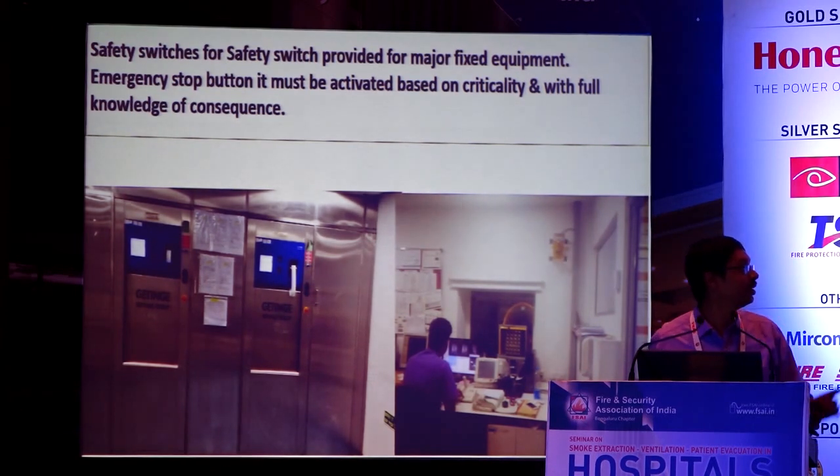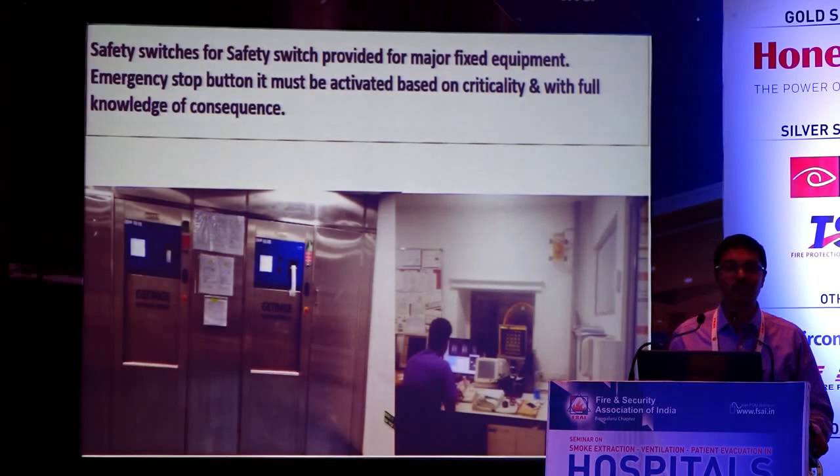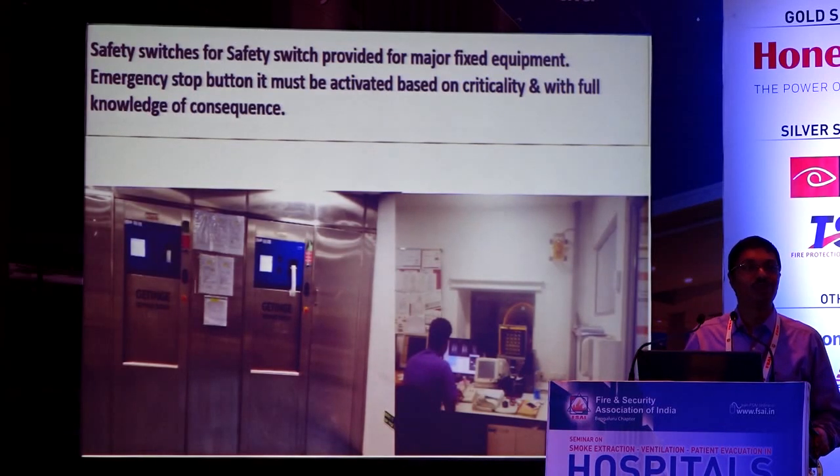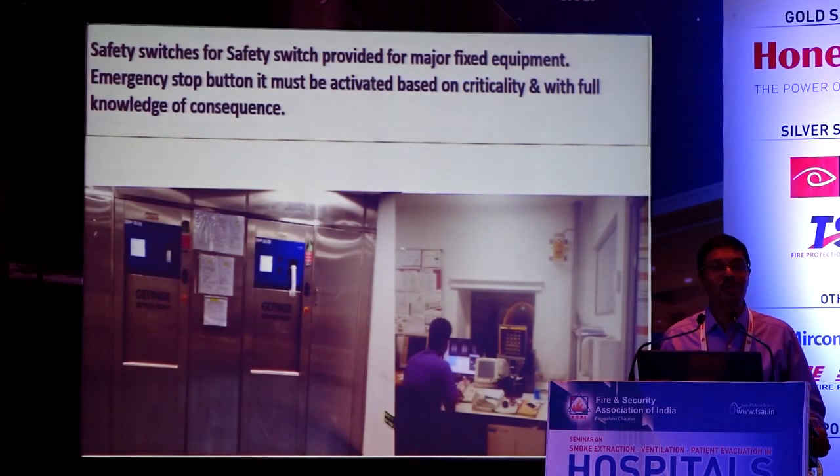The safety switch can be used only when it is needed, when somebody is stuck, because when you use that safety switch, the magnet loses power, it quenches. Then to ramp up the magnet again, you will have to spend at least 1 crore. So people have to know the significance of each of these safety switches, when they are to be used, and who has to use them.